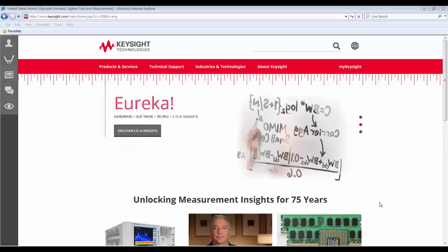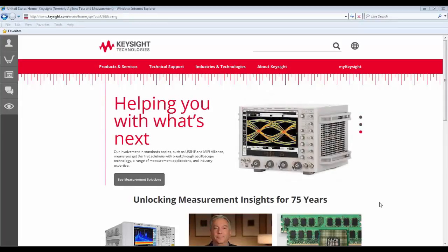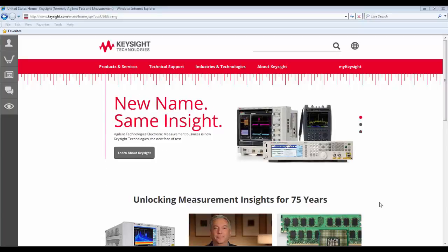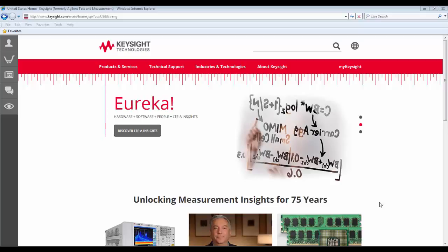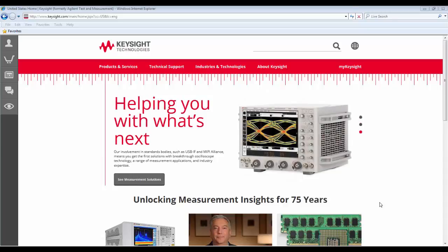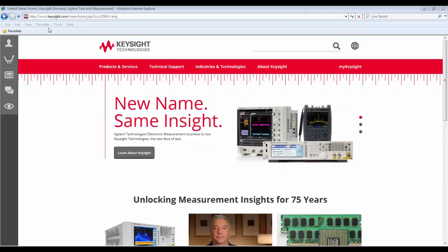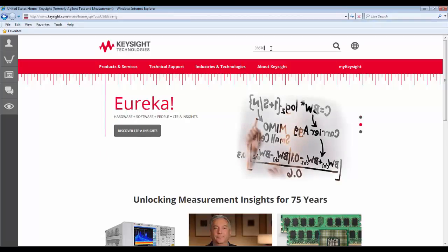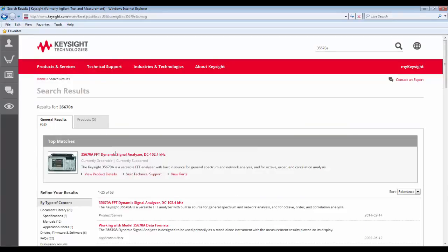If you do not have the most current firmware, you can download it for free from the website or order it as part number 35670U, option UE2. Oftentimes customers choose to order the floppy disks because the free download requires older Windows versions and floppy disks. However, if you do wish to download the firmware from the website, you can do so from www.keysight.com. Simply put the product number 35670A into the search term, hit enter, and wait for the top match to appear.